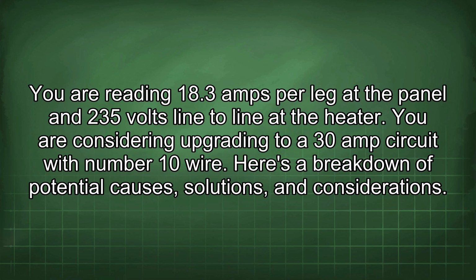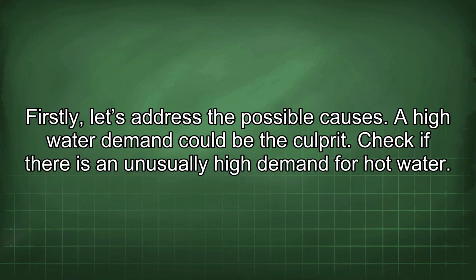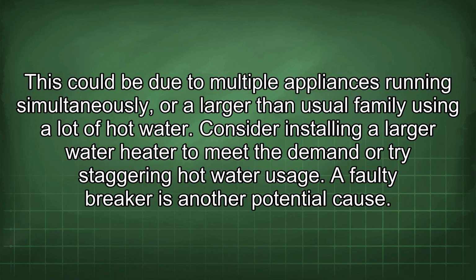Here's a breakdown of potential causes, solutions, and considerations. Firstly, let's address the possible causes. High water demand could be the culprit. Check if there is an unusually high demand for hot water. This could be due to multiple appliances running simultaneously or a larger than usual family using a lot of hot water. Consider installing a larger water heater to meet the demand or try staggering hot water usage.